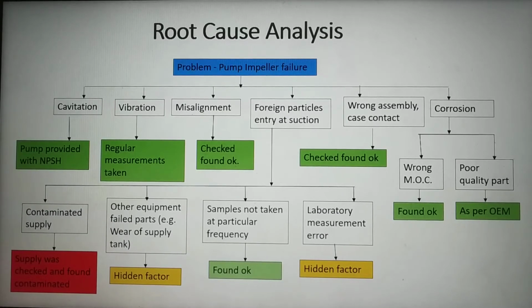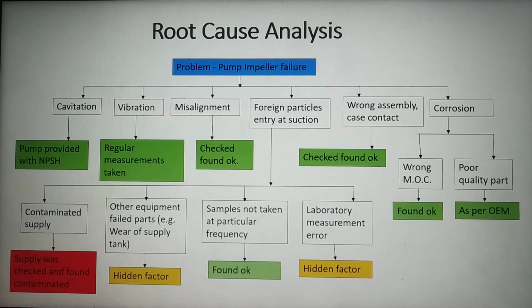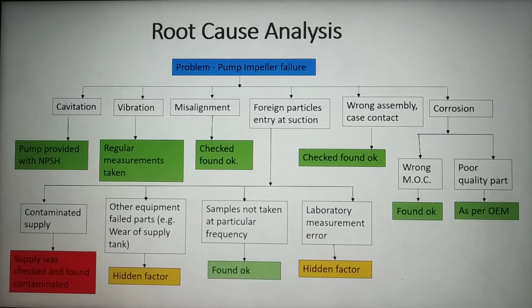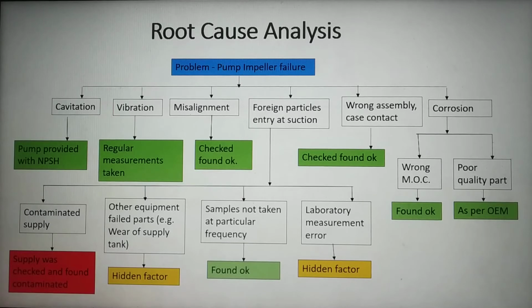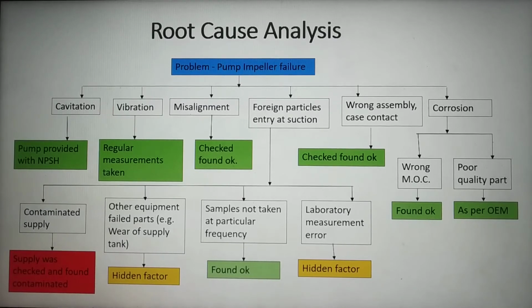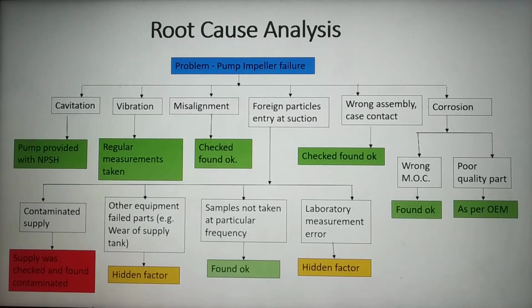Suction means pump suction. So first is contaminated supply. The supply we are providing, any liquid to the pump, can be contaminated, and it is marked with the red that the supply was checked and found contaminated. So what it means is that we checked this reason and found that yes, this is the cause for the pump impeller failure. Okay, so let's move to the next.